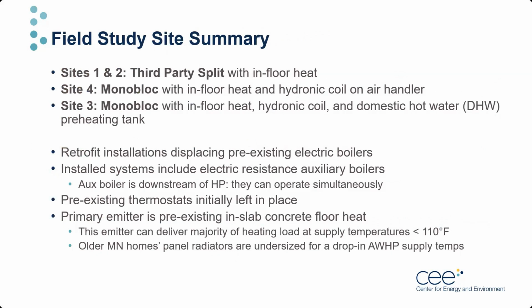This field project installed 2 third-party split air-to-water heat pumps and 2 monoblock systems. The split systems were paired simply with radiant floor heating, with no cooling or domestic hot water capability. The monoblocks were paired with radiant floor heating and a central hydronic coil on pre-existing air handlers that allows them to provide heating and cooling. One monoblock site was also configured to support domestic hot water by heating a domestic hot water preheating tank. All installations replaced existing electric boilers and essentially kept a balance of system components in place. The primary emitter for all homes was the radiant floor, which is compatible with AWHP supply temperatures. And we had concerns about retrofitting high temperature panel radiators that could be undersized for the lower supply temperatures that come with a heat pump retrofit. Next slide.